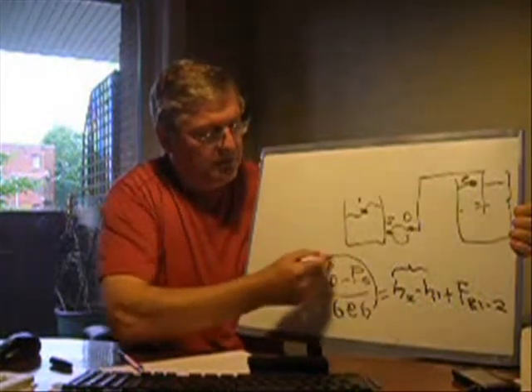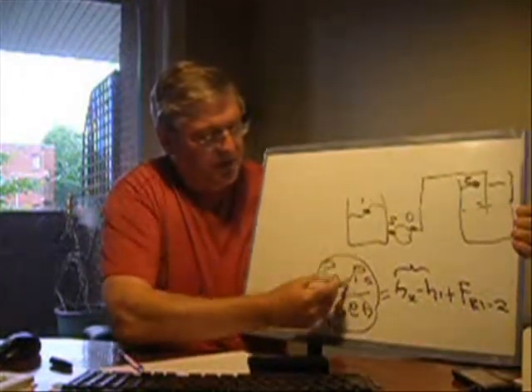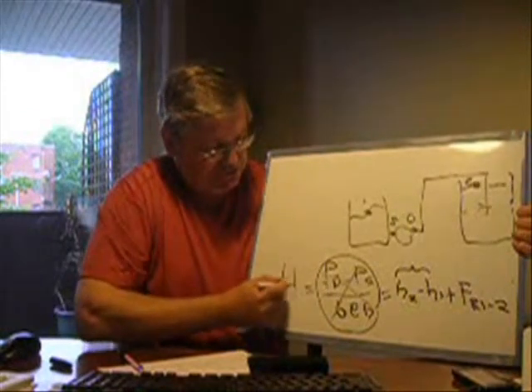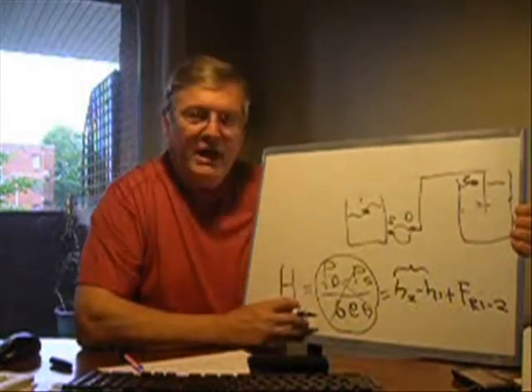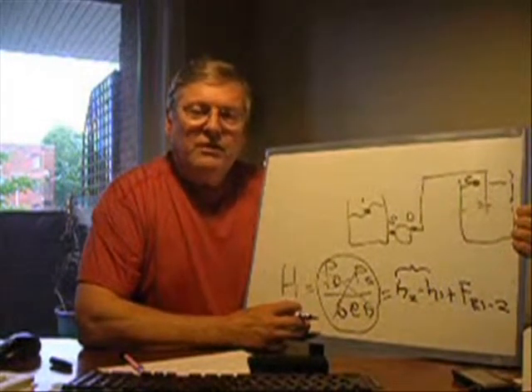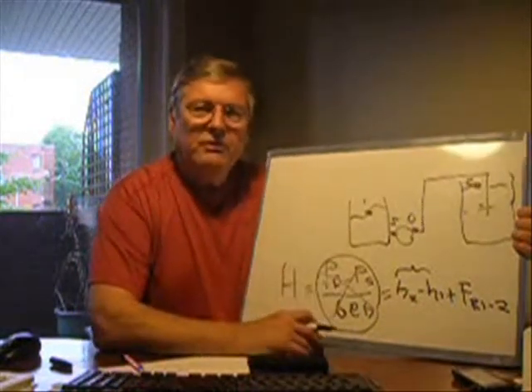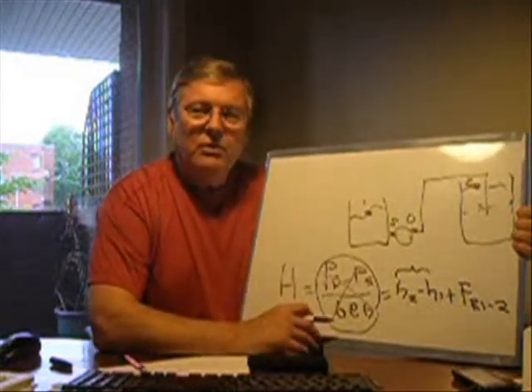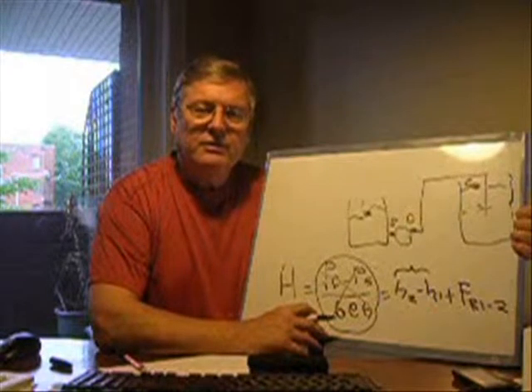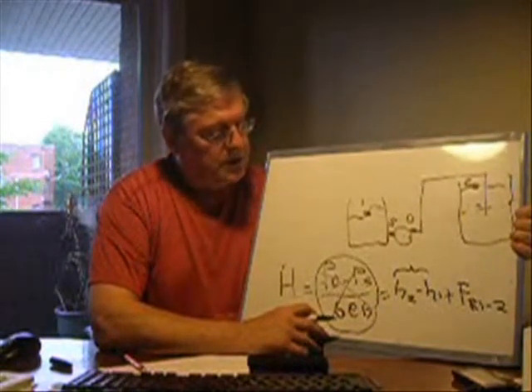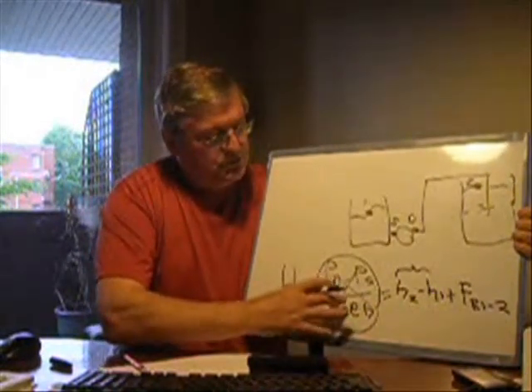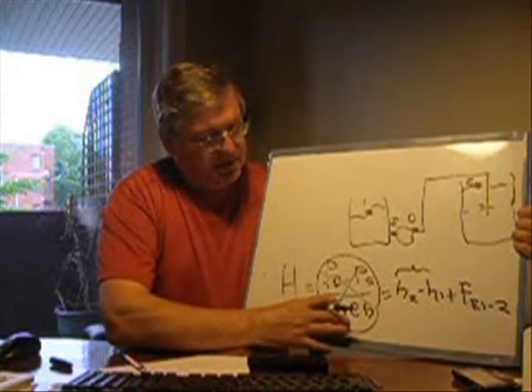If we add static head and friction head together, we get the amount of head the pump needs to provide. I've lumped this whole term together and called it H for head — that's known as the total head of the pump. Once I have these two numbers, I can go to a store, look up a pump graph, and select the right pump for the job.